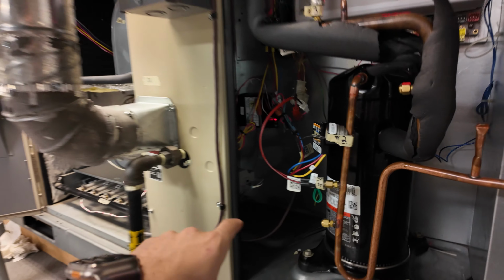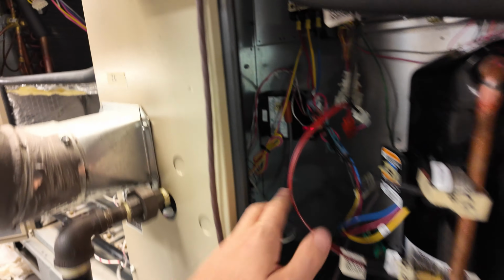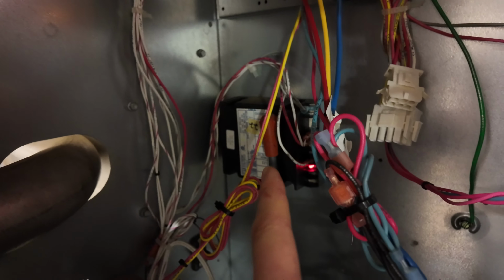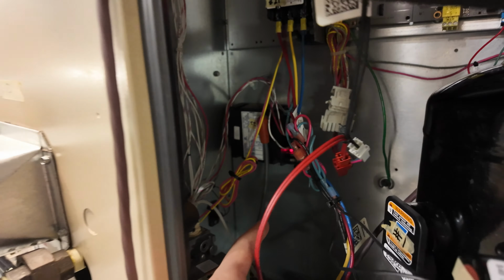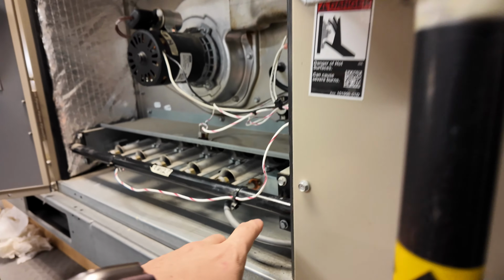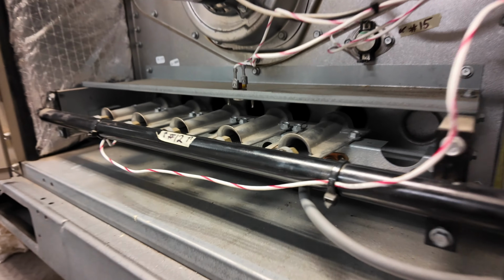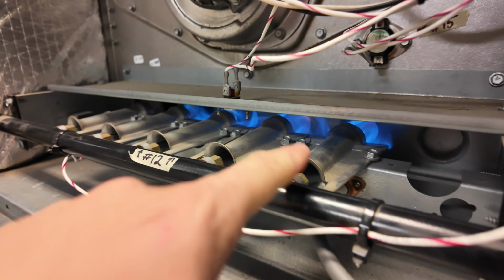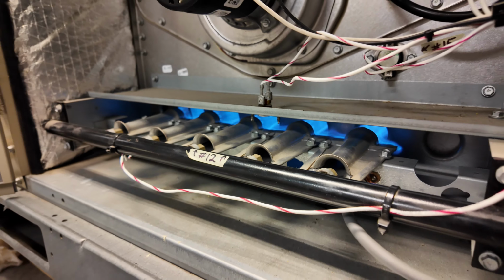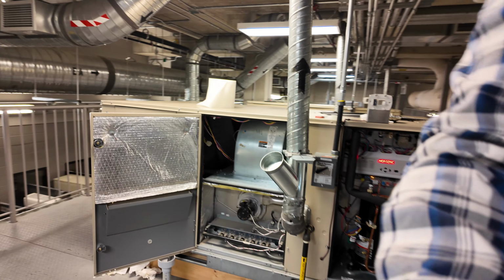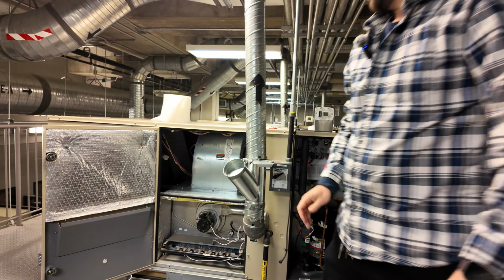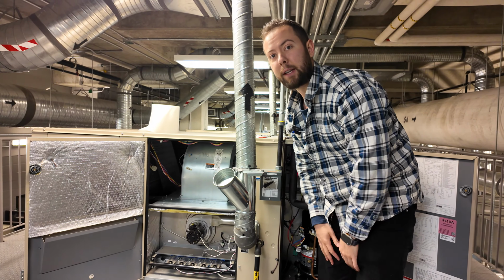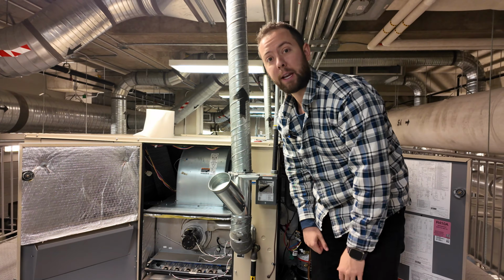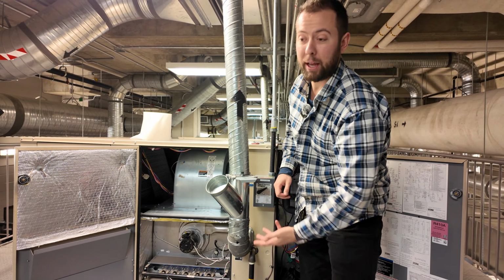Then it's going to energize that gas valve, and this is where the ignition board is. The ignition board is going to send high voltage through the ignition cable, and we'll watch these burners. They're going to light here and flow across. So that's the kind of base cycle for this Lennox unit. It's pretty simple. Like I said, I really like these.